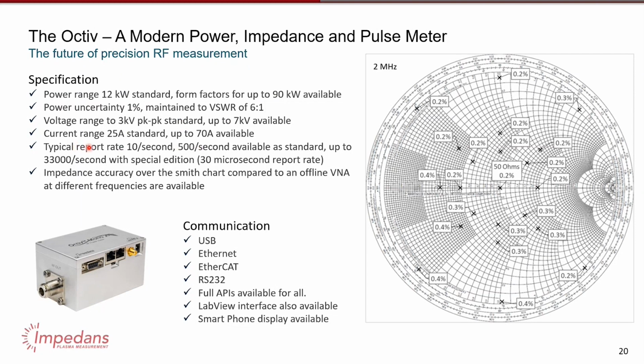You can also do this rapidly. So, like, with a VNA, it's a very offline tool. It's quite slow to use, but these VI probes can go quite fast. So our standard VI probes can report up to 500 times a second if you want. Adjustable. Yeah, and you get more communication options. I've seen people use VNAs that are old and they have to use a floppy disk to get the data and transfer it to a computer to map out the impedance of a plasma or impedance of a load. So just to add a lot of convenience.